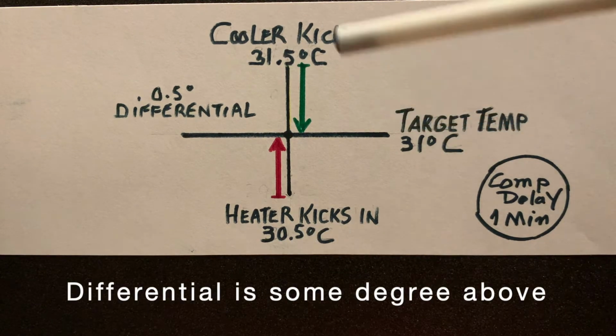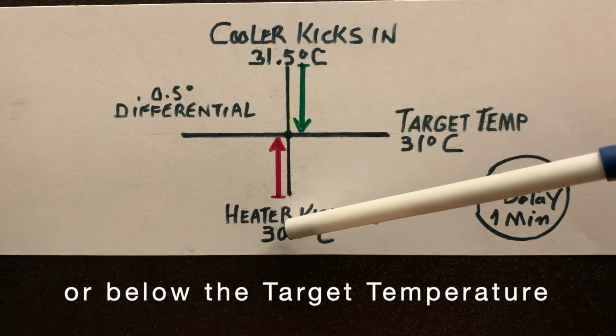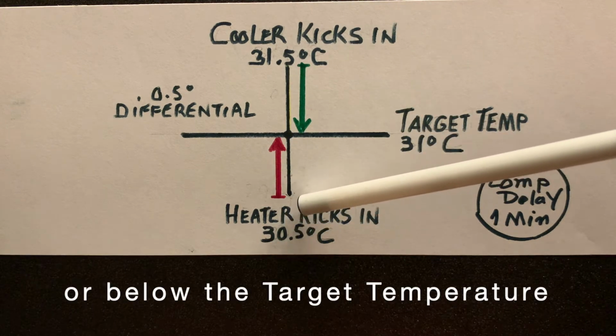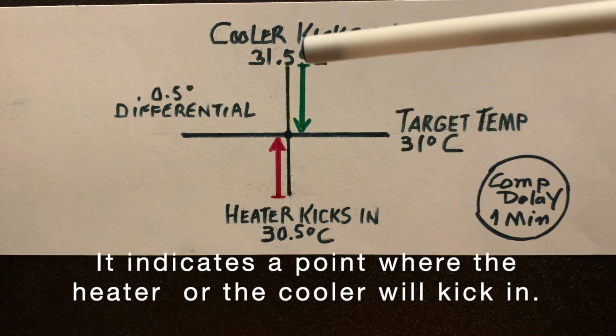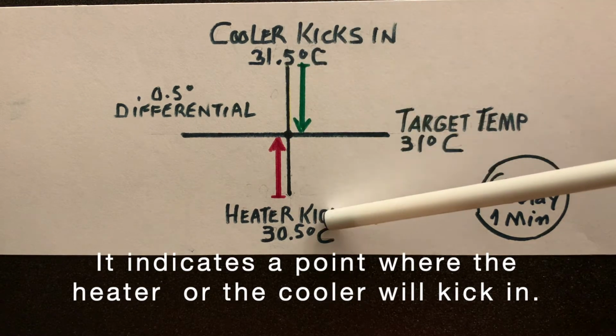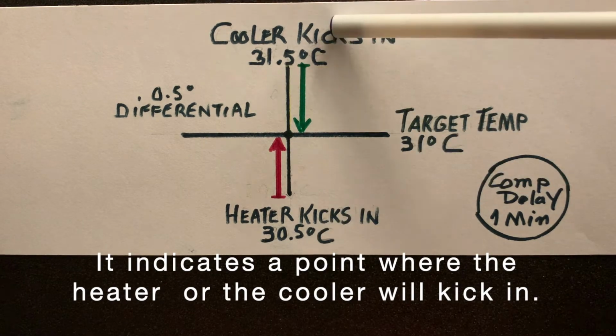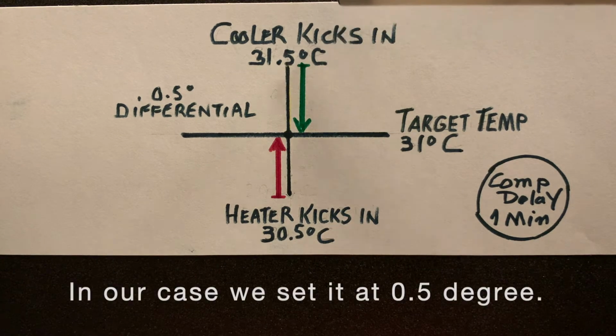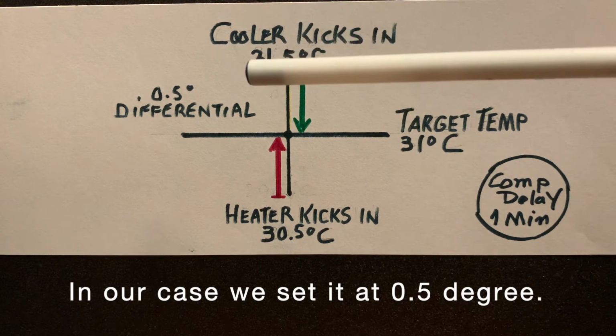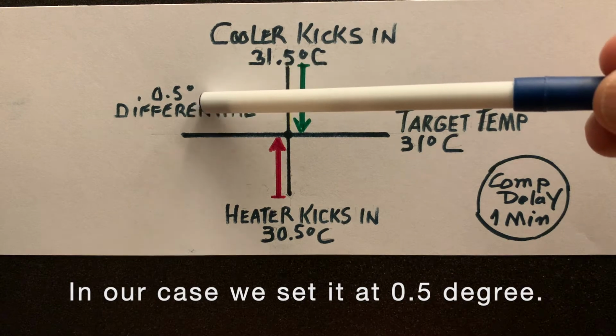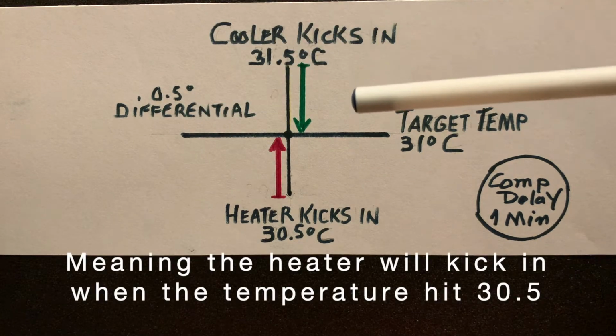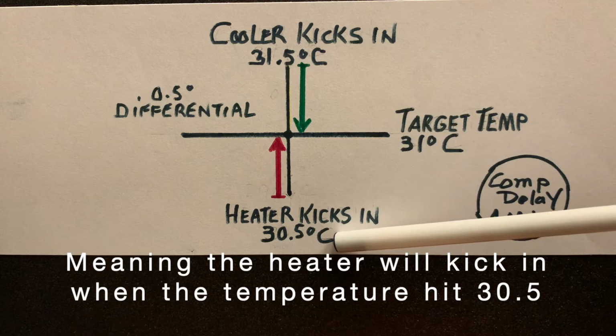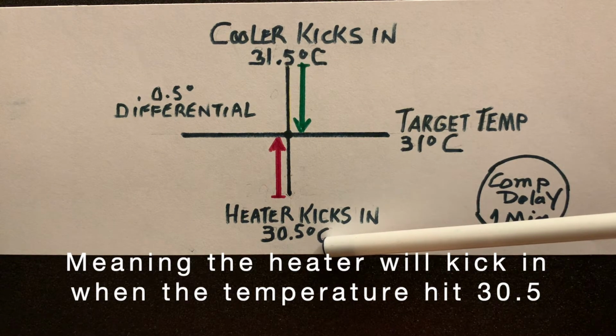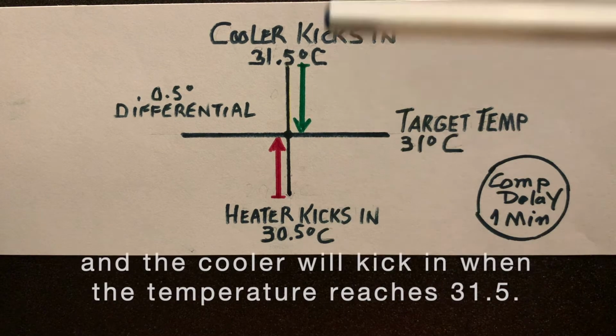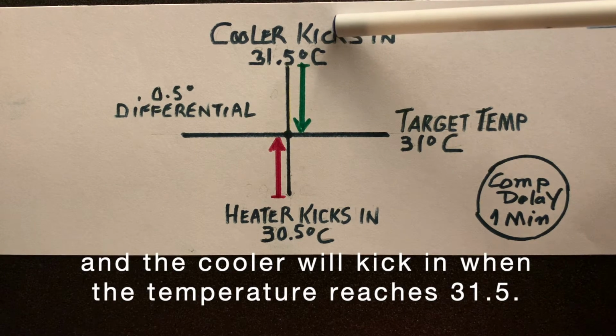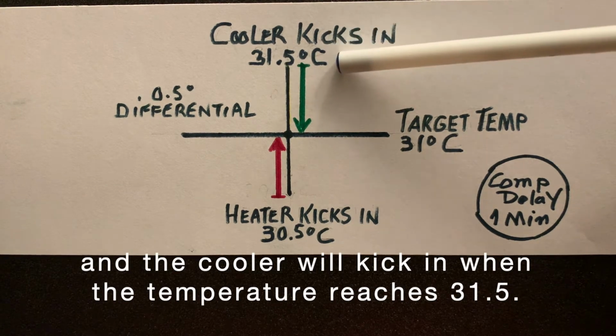Differential is some degree above or below the target temperature. Indicates a point where the heater or the cooler will kick in. In our case, we set it at 0.5 degree, meaning the heater will kick in when the temperature hit 30.5 and the cooler will kick in when the temperature reaches 31.5.